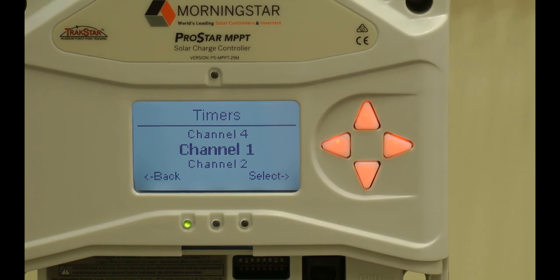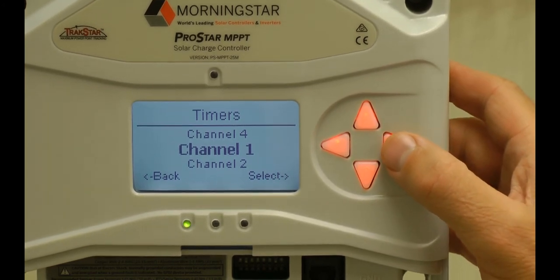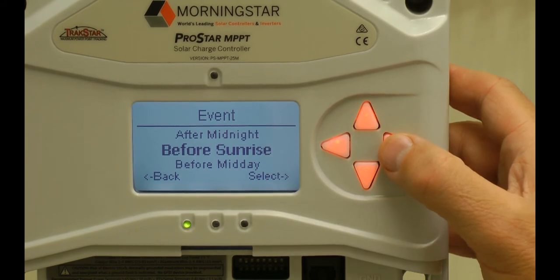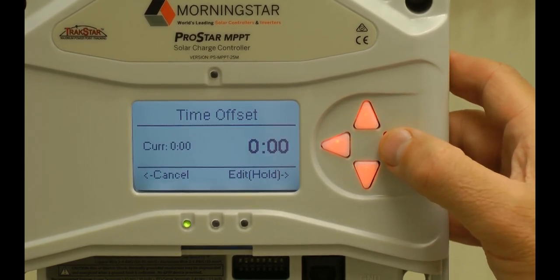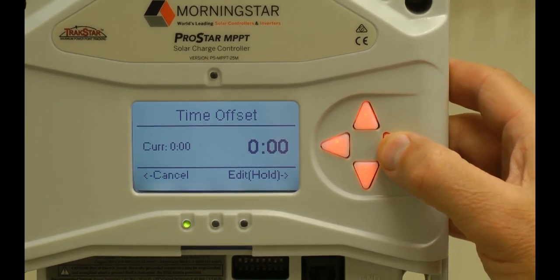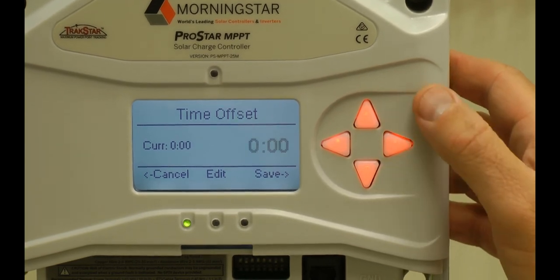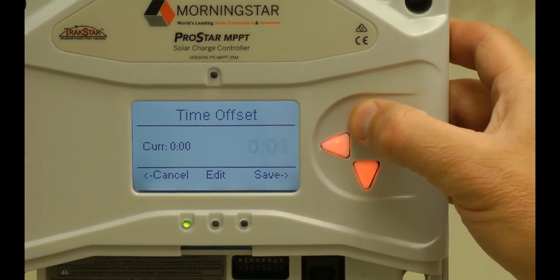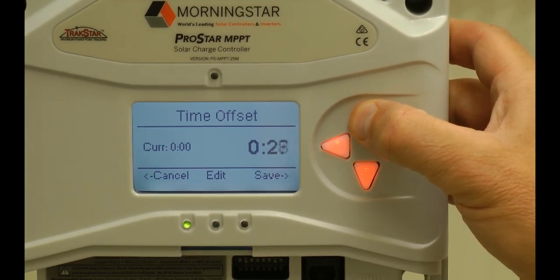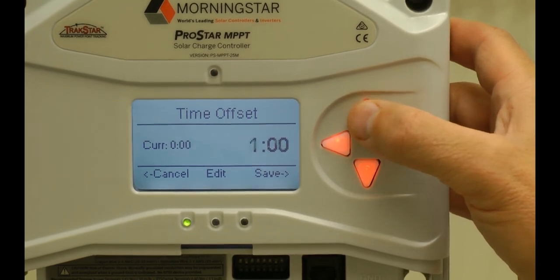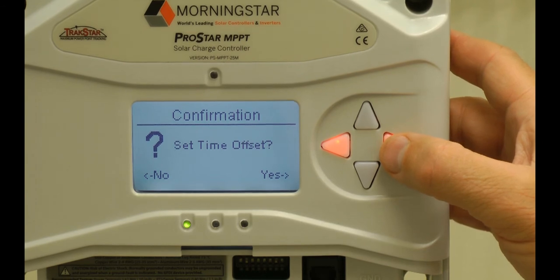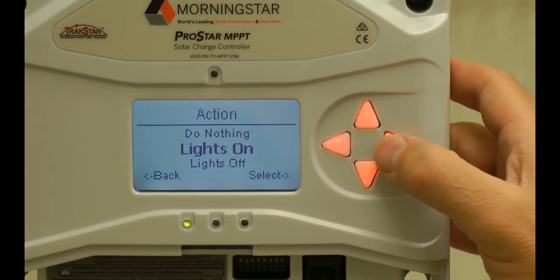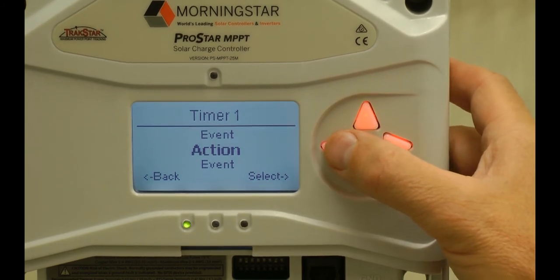Let's begin with channel one, which we're going to use for programming our sunrise. Channel one, timer one — the event is going to be before sunrise. Press and hold the right arrow button to actually edit the timer, and it will start flashing to let you know when you can change it. We wanted to set timer one to be one hour before sunrise, so we'll select one hour and save. It will ask you to confirm — you say yes. And the action on that timer is going to be lights on. So we've set timer one to turn the lights on one hour before sunrise.